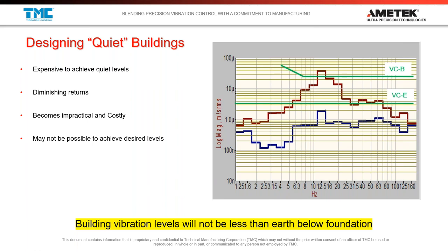Another problem that we see is folks trying to design quiet buildings. Well, quiet buildings aren't really the answer, because you can make your slabs as beefy and filled with as much mass and concrete as you possibly can, but it gets more and more expensive and you start to achieve diminishing returns. And the important thing to remember is that your building vibrations won't be less than the earth below it. So if you've got noisy ground from trains and traffic and whatever else is going on outside, you can build a building as massive as you possibly can, and it still won't be less than the earth below it. And you won't be able to fight the fact that the vibration levels in facilities are rising over time.